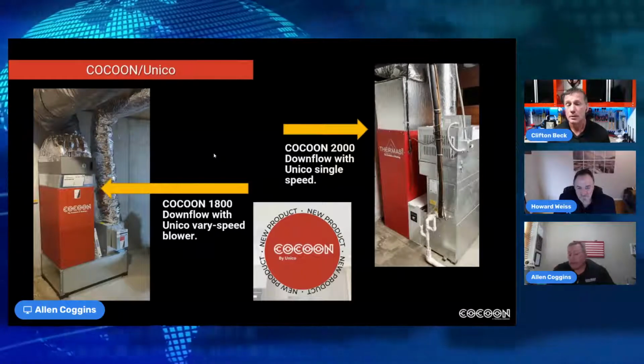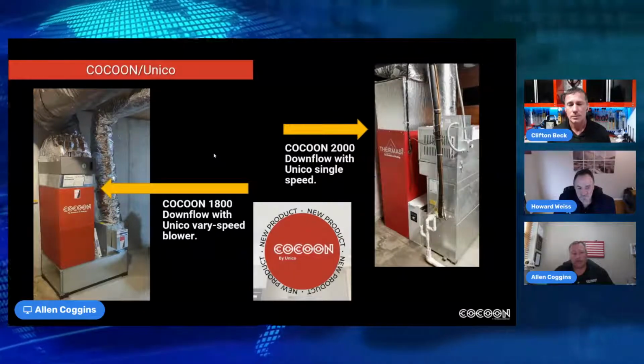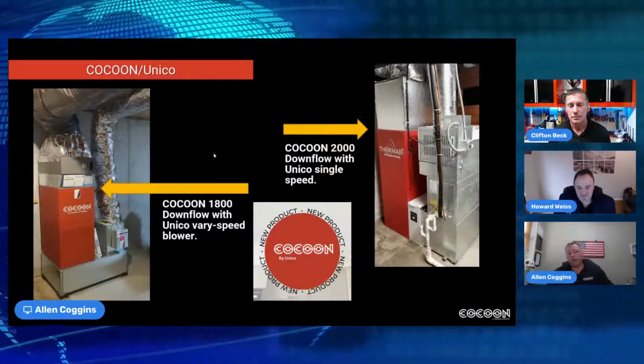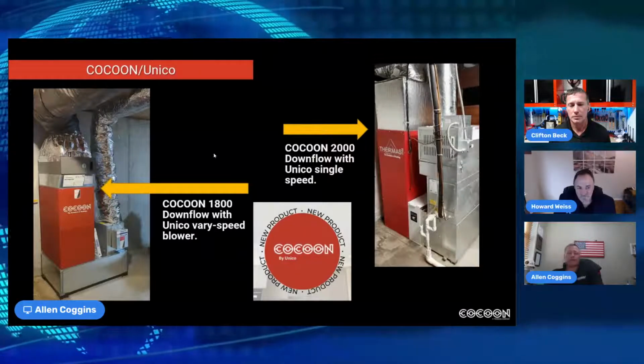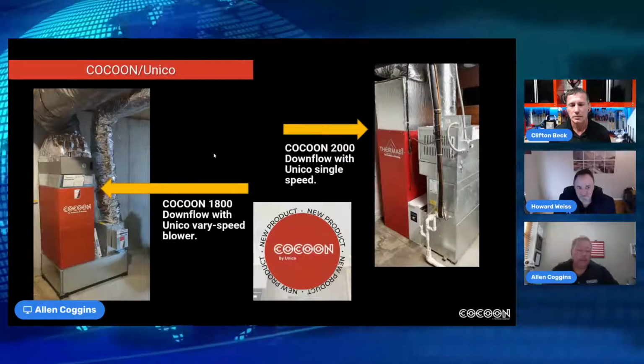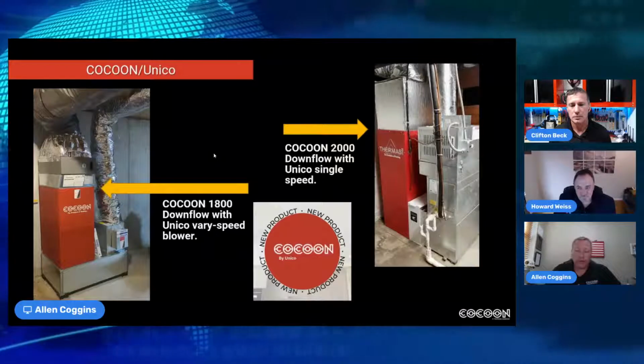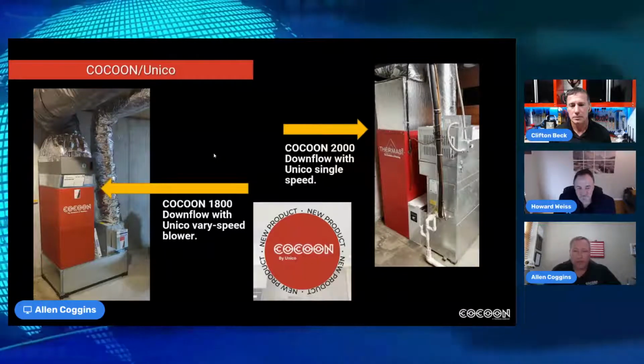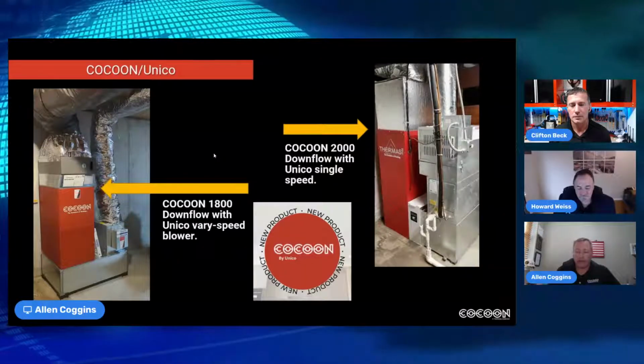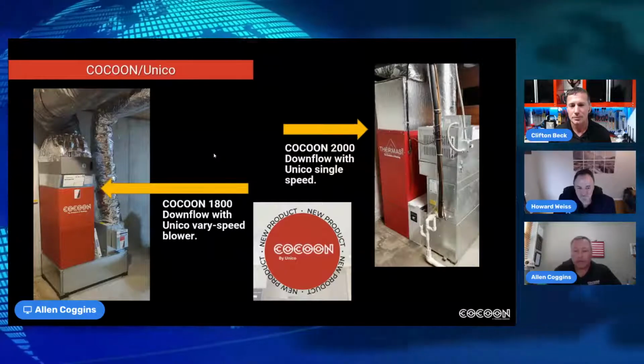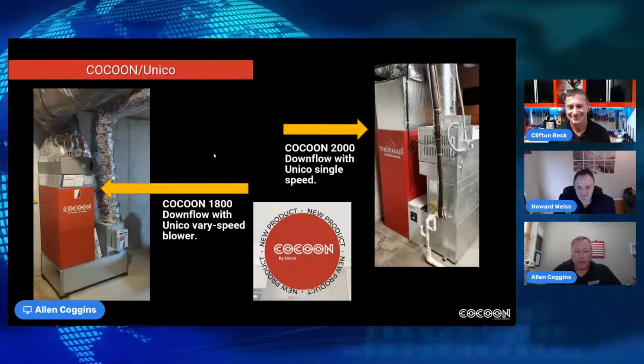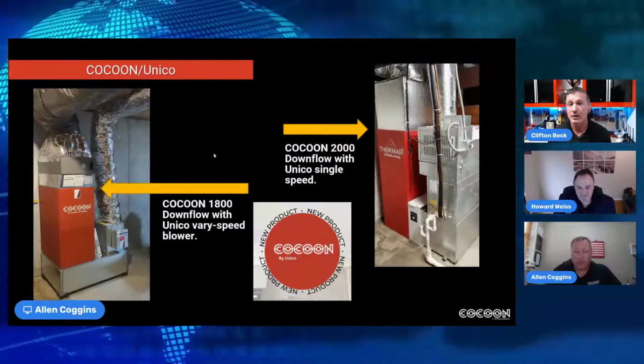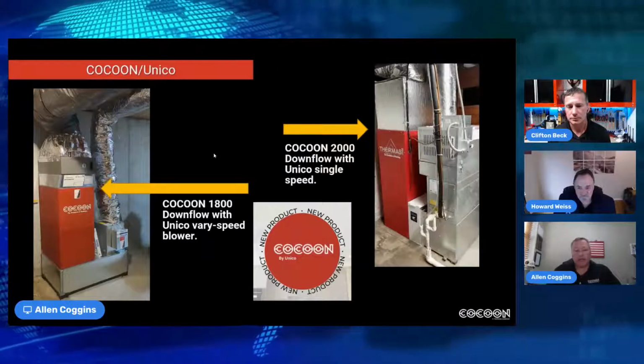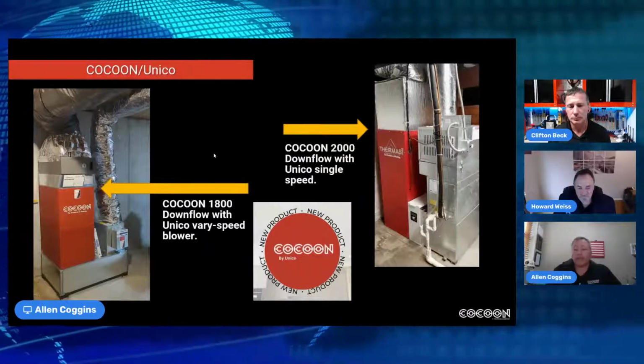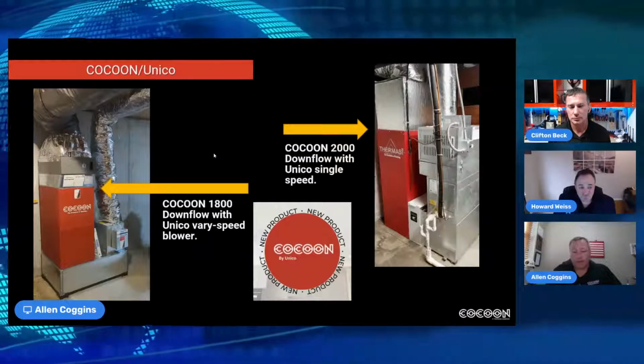Or they didn't have the space to put in conventional ductwork, so high velocity works well. But when you start looking at high velocity and let's say you need a 20 kW furnace, your pressure drop - they're fitting 10 pounds of crap in a 5-pound bucket. The pressure drop across them is massive, very significant. So we offer a better heating solution when it comes to high velocity systems.